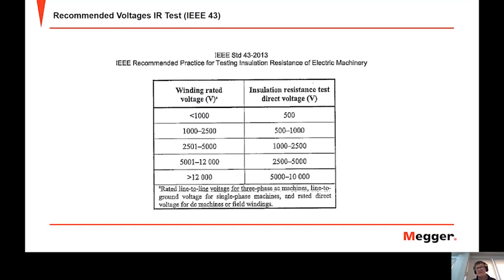So it's important to look at the standards and to understand what the standards say, certainly in terms of applied voltage. So for the IR test, which also covers the PI test, we can look at the IEEE 43-2013 standard. And this is the recommended practice for testing insulation resistance of electrical machinery. So if we look at our winding rated voltage, so less than 1,000 volts. So now we're talking of 400 volt motors, 690 volt motors. The recommended insulation resistance test voltage is 500 volts DC.